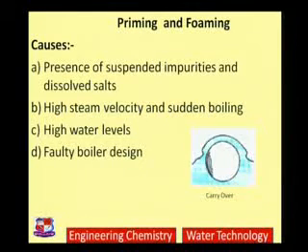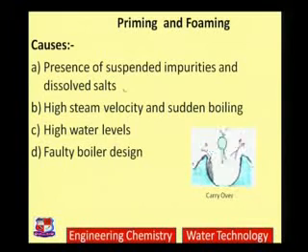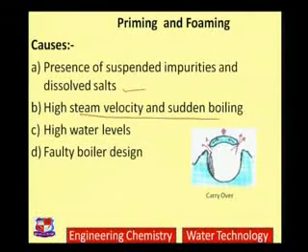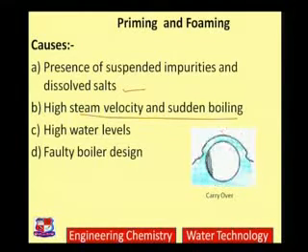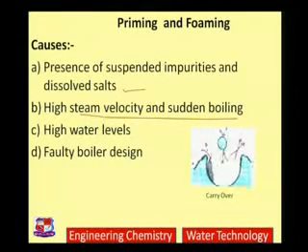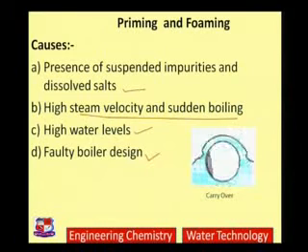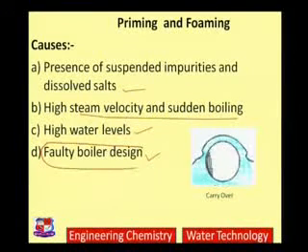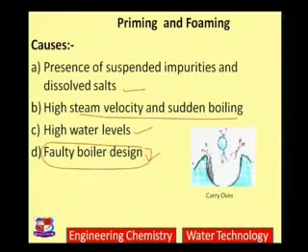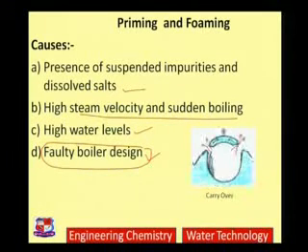The causes of priming include: presence of hard water, presence of suspended impurities and dissolved salts, high steam velocity, and sudden boiling. If sudden boiling occurs in the boiler, or if the rate of steam formation is increased rapidly, priming can happen. If the water level is not adjusted properly and is kept very high, it may also lead to priming. Faulty boiler design or engineering mistakes can also cause priming. Here you can see wet steam formation happening in the boiler.